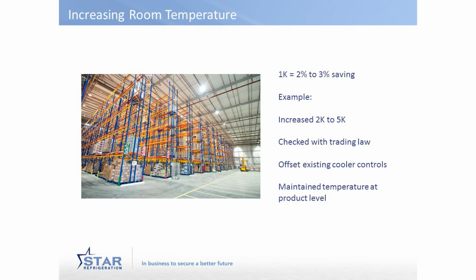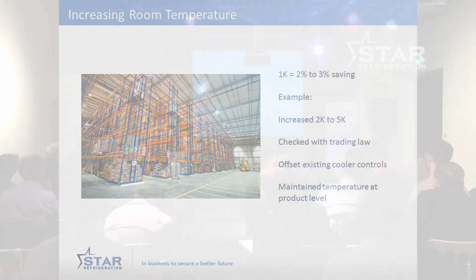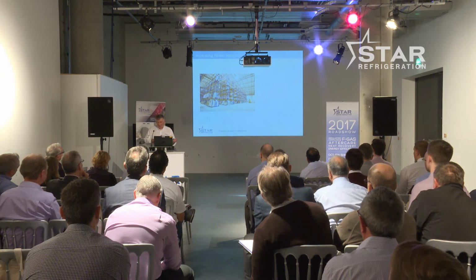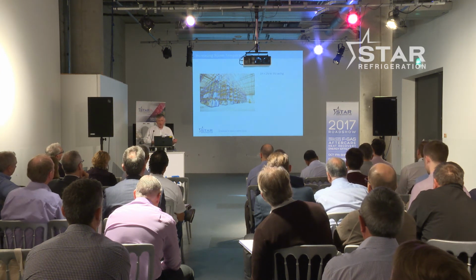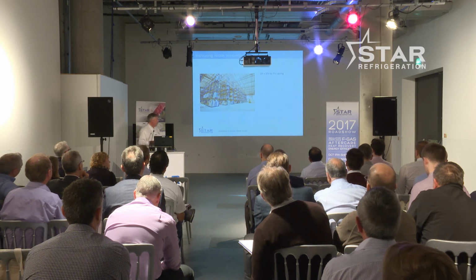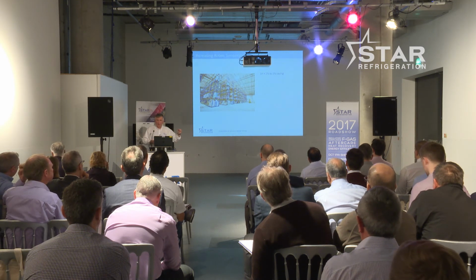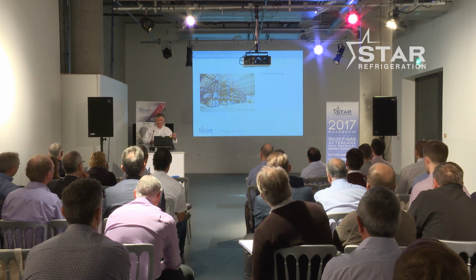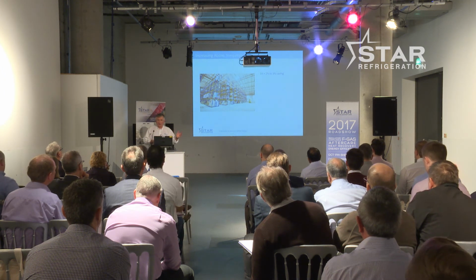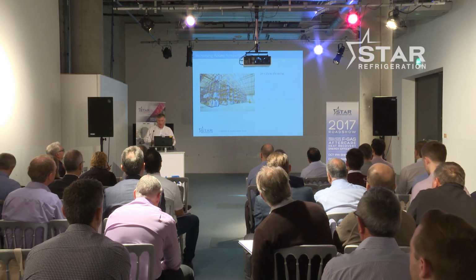Retailers have asked us over the years to look at their energy consumption and come up with ways that we can improve things. In one case, we were able to increase the storage operating temperature by 2 degrees C without having an adverse effect on the product, and delivered a significant saving to the end user in energy terms. And I'll just very briefly talk through the background to that. So raising the compressor operating temperature, the cold end of the compressor, by 1 degree C will save between 2 and 3% of the energy that the compressor is consuming.